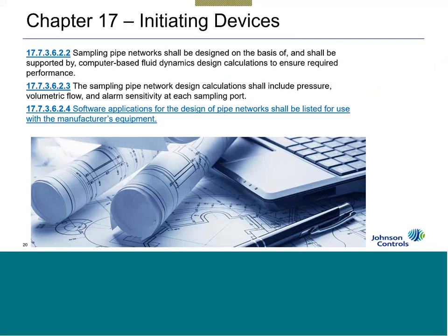Additionally, if you are going to use software, it's got to be something that's listed for use with the manufacturer's equipment. There have been several cases where people are using Excel spreadsheets, rule of thumb, drawing it out, and just kind of guessing where these sampling ports should go, the size of the holes. So the code had to be changed, and in 2019, 17.7.3.6.2.4 was added, which blue is new. Software applications for the design of these networks shall be listed for the use with the manufacturer's equipment.